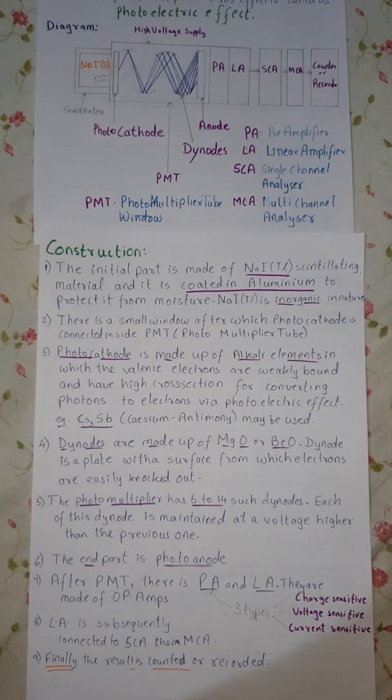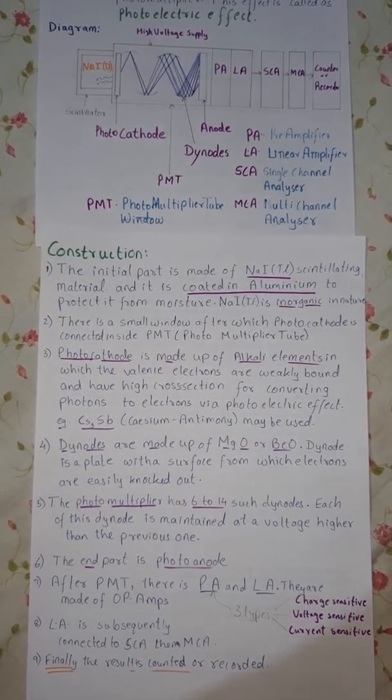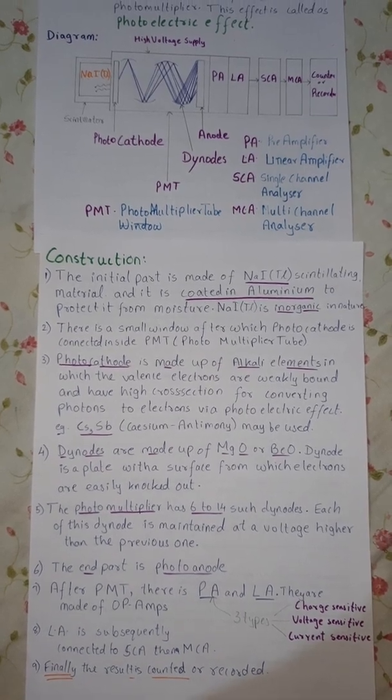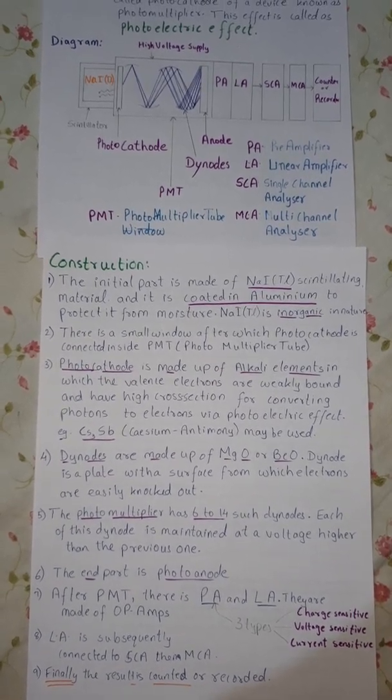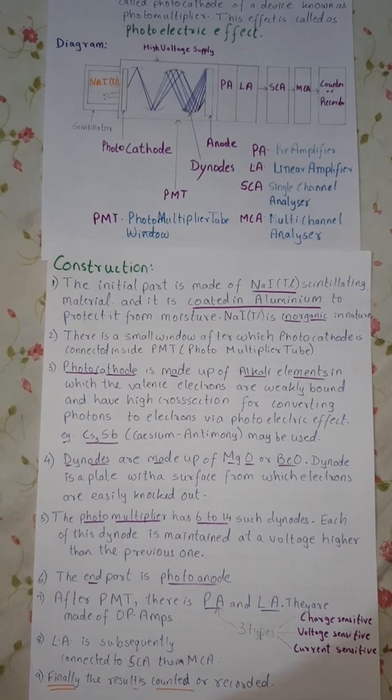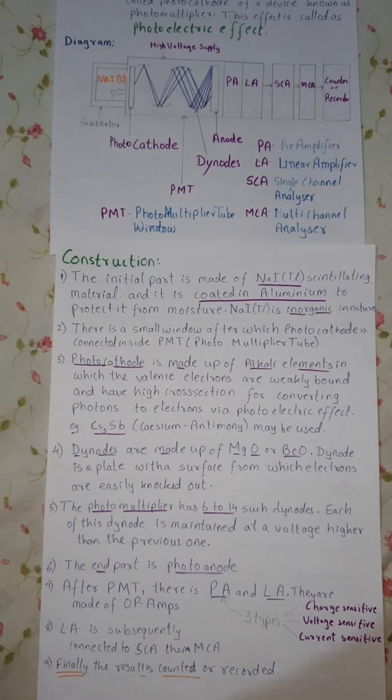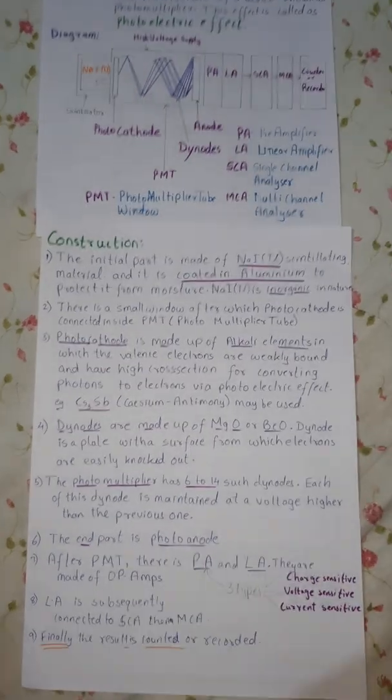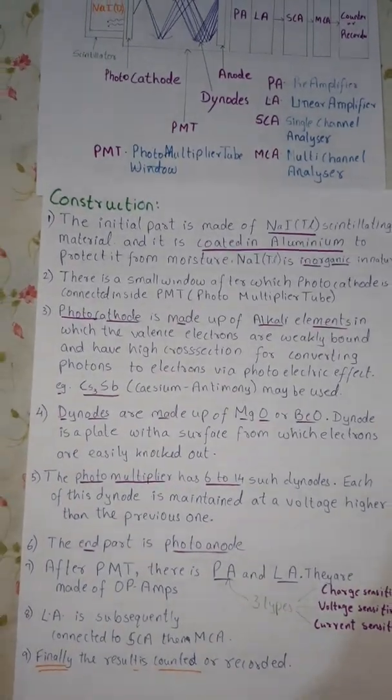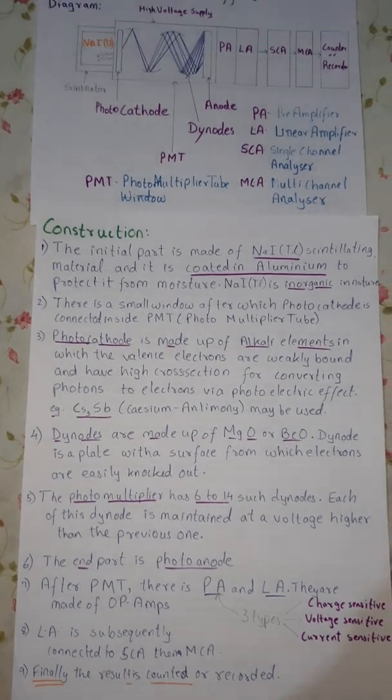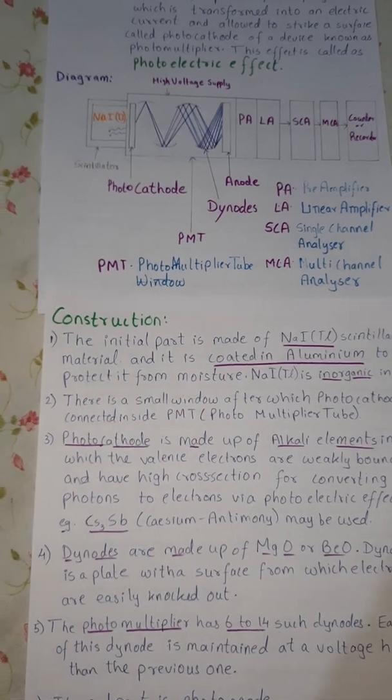Next is the dynode. The dynodes are made up of magnesium oxide or beryllium oxide. Dynode is a plate with a surface from which electrons are easily knocked out. The photomultiplier has 6 to 14 such dynodes. Each of these dynodes is maintained at a voltage higher than the previous one. For example, if the first dynode has a potential of 100 volt, the next one will be 200 volt and subsequently it increases.